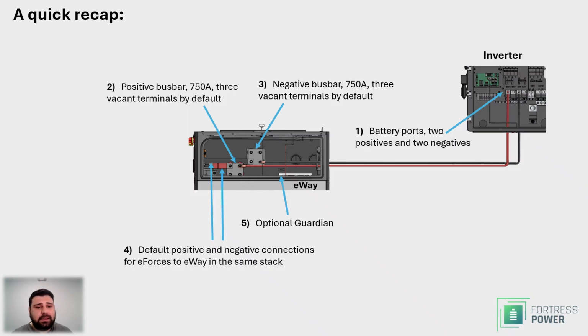Then inside the eWay we have positive bus bar, 750 amps, and negative bus bar, which is also 750 amps. By default, you have one of the ports on this bus bar occupied by the positive and negative connections. So right here you see positive and you see negative. With these connections in place, which are default and always there, you have 3 vacant ports available.